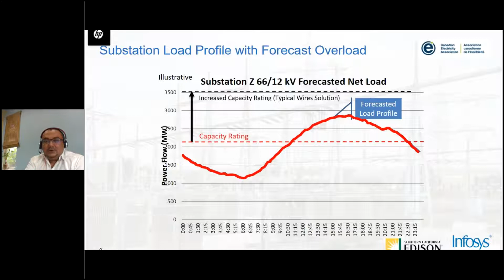So I'll use this duck curve as a quick demonstration of the thinking process behind the entire DER solution. We're showing here just a load profile at a substation, which is 66 to 12 kV. It's a forecasted load profile. Maybe 5 years down the line, we're seeing that the load or energy needs have crossed the capacity rating of that substation. In a typical world, what we would do is use a wired solution - try to increase the capacity of that substation to meet the increasing demands. But here we're going to show how the DER solution, along with the other levers we have with the utilities, can be a substitute to that typical capital solution.